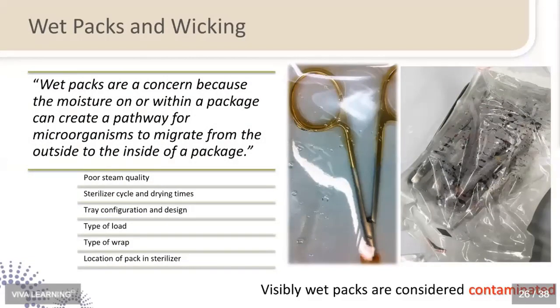Another issue that comes up often is wet packs and wicking. When you are choosing the right size pouch or the right size wrap for your cassette, and you're putting in the correct amount of instruments, and you are loading that sterilizer with best practices of vertical loading and use of racks on the shelves, this is going to allow for the 360-degree circulation of the sterilant, and it also then allows for 360 circulation of the dry air to dry it. If you put instrument cassettes one on top of each other, you're not going to be able to get 360-degree penetration or circulation of the sterilant. And so this is one of the main reasons. Overloading or misloading of the sterilizer is the #1 reason for wet packs.